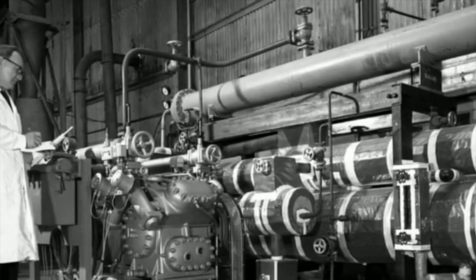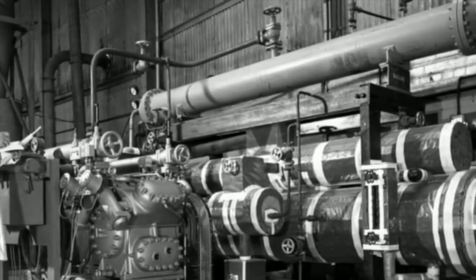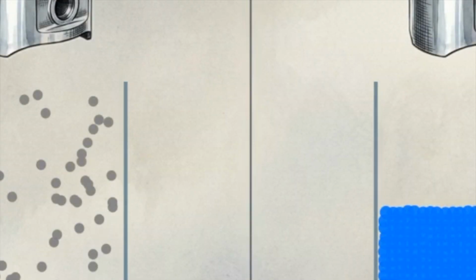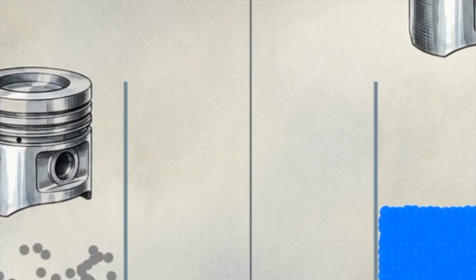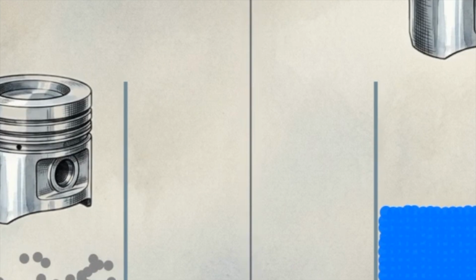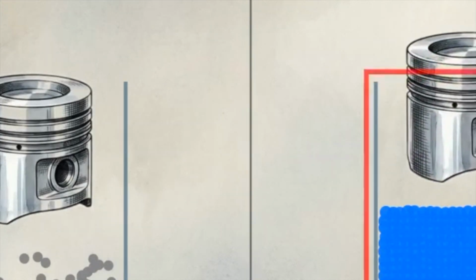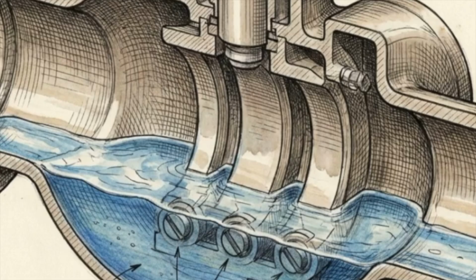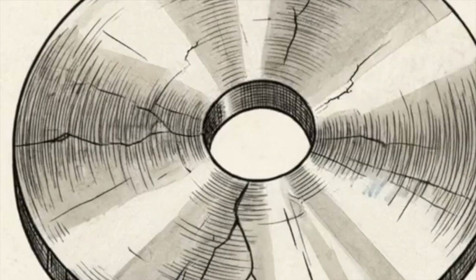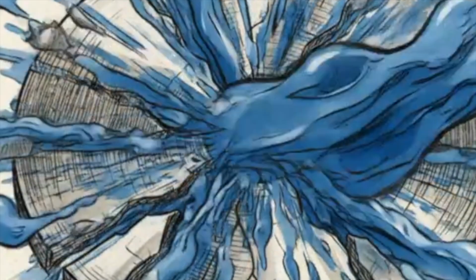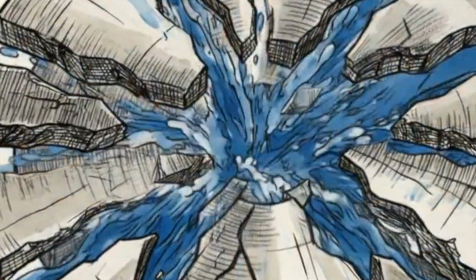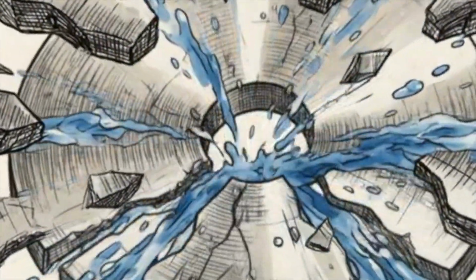Facilities expect these massive machines to run flawlessly for decades without a single interruption, but they operate under a rigid law of physics. Compressors are built strictly to compress vapor. Liquid, by definition, is incompressible. If a system loses superheat stability, liquid refrigerant enters the compression housing. This is known as liquid slugging. The mechanical valves attempt to compress this liquid, and the resulting hydraulic pressure instantly shatters the internal steel components.